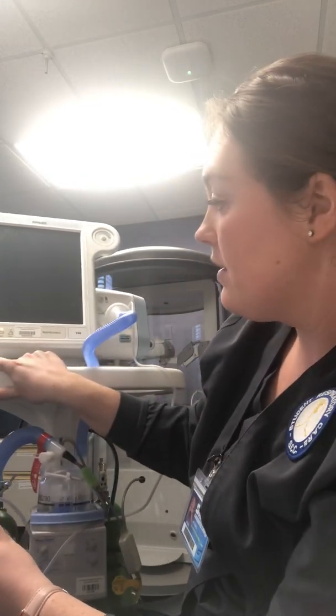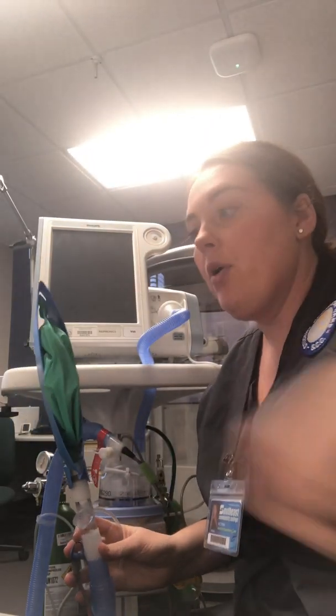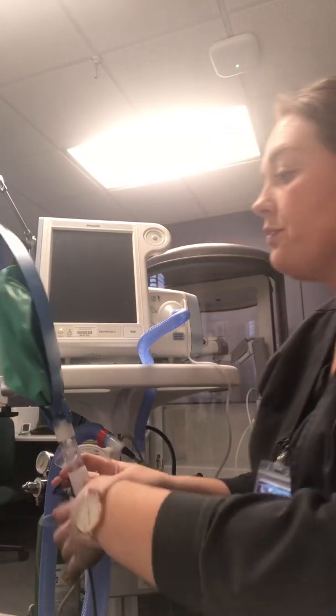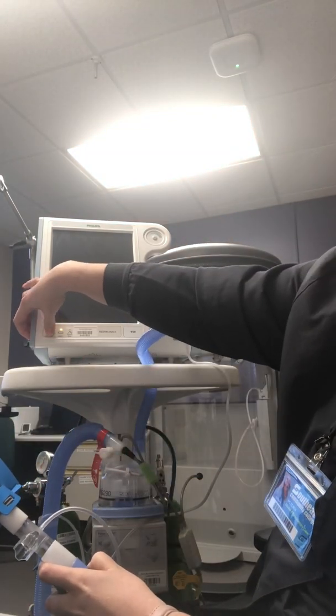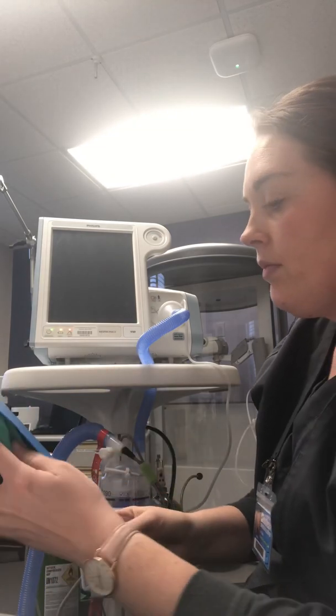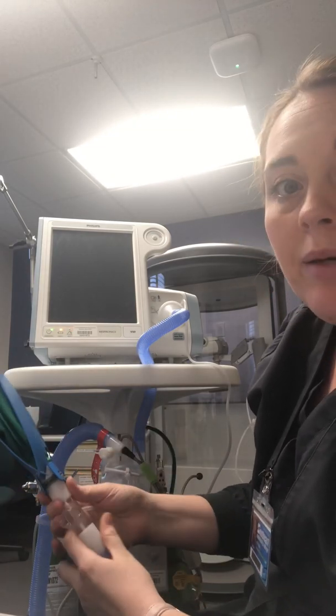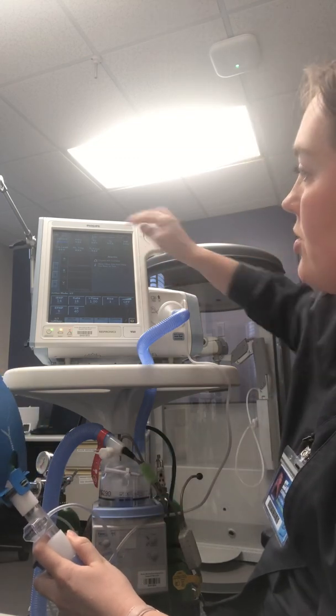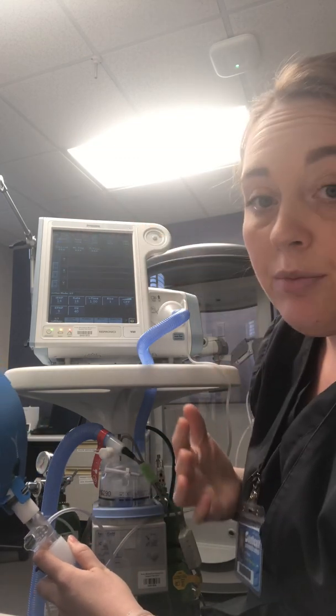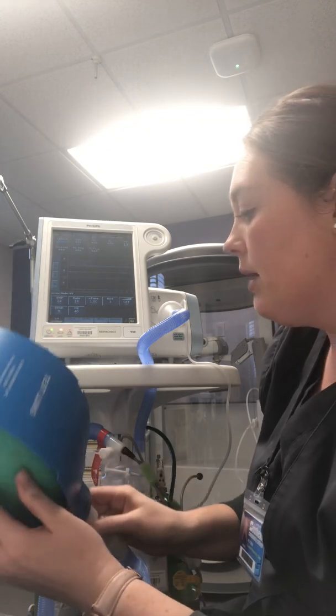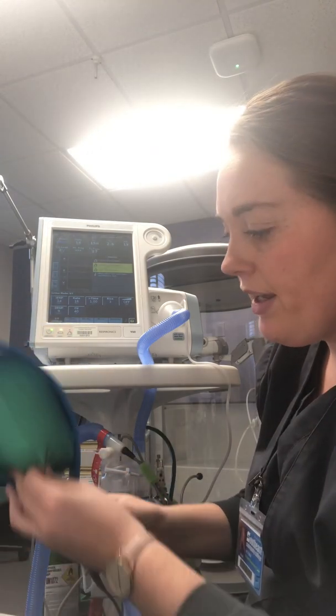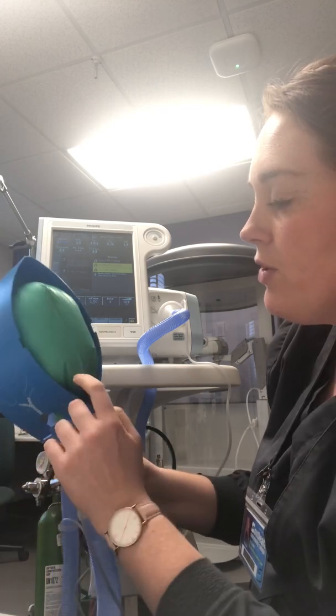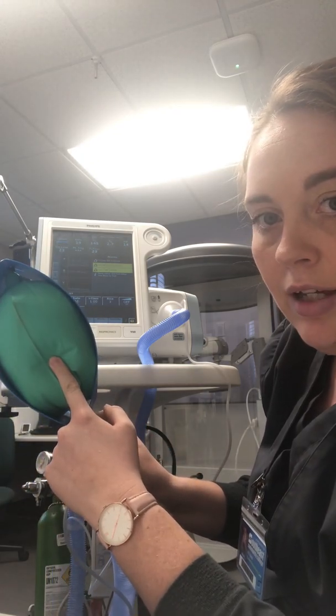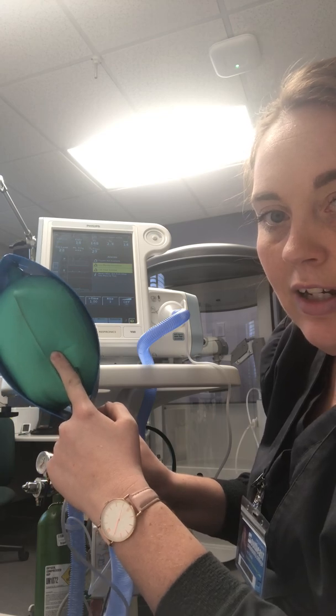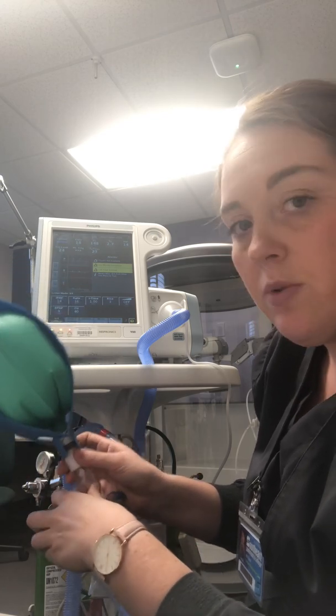So I'm going to go ahead and bring this a little closer, and we're going to talk about the settings and how to adjust the settings on the Bipap. So you just go ahead and push the on button here. I'm going to get an alarm right away that's going to tell me my oxygen's not available. I'm not going to put oxygen on there, but just so we know. I'm going to kind of show you this as best I can with this test lung, so you can see the difference between the IPAP and the EPAP. Okay, that's exhalation, inhalation. So you can see that there is a pressure difference between the two.